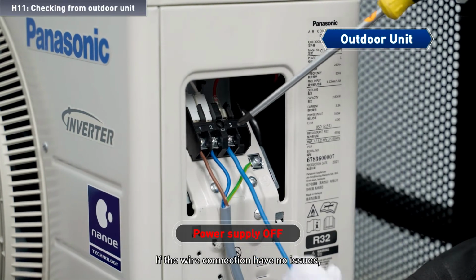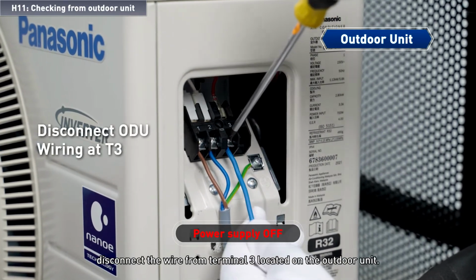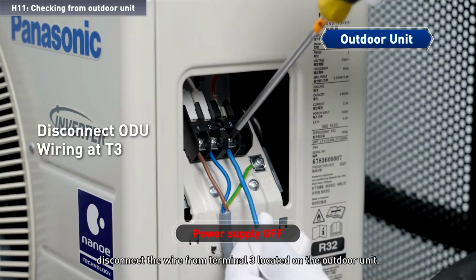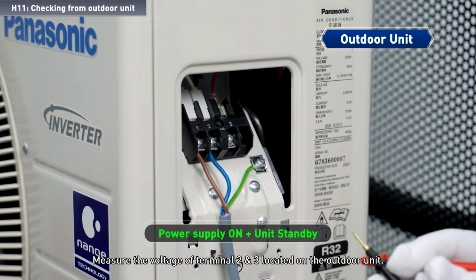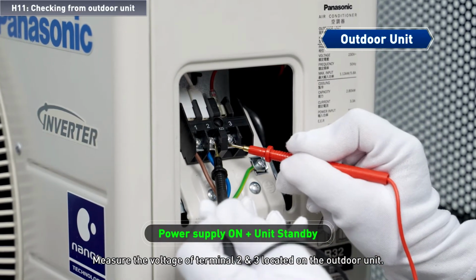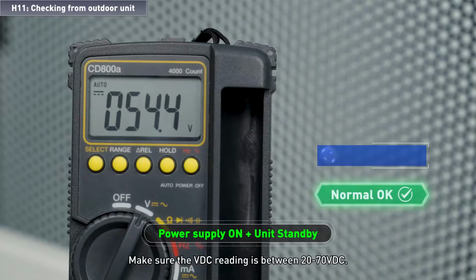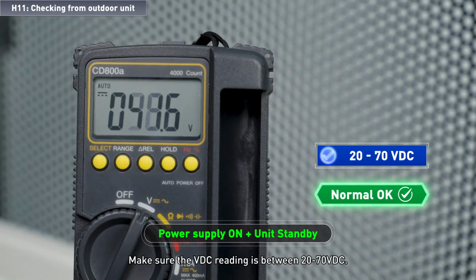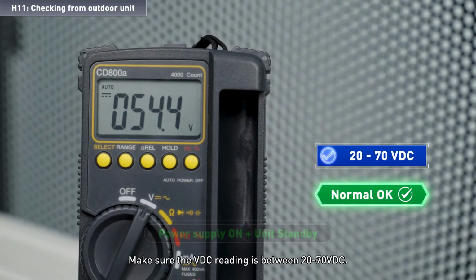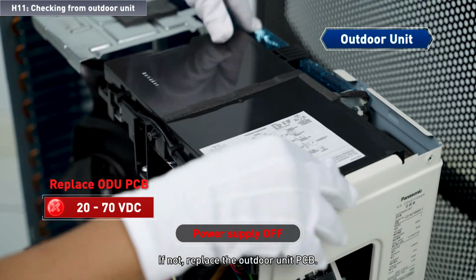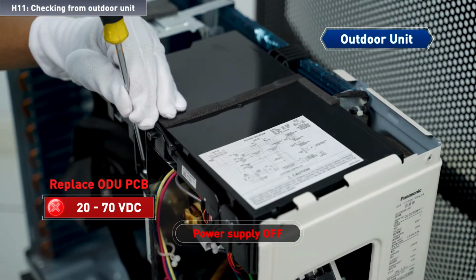If the wire connection have no issues, disconnect the wire from terminal 3 located on the outdoor unit. Measure the voltage of terminal 2 and 3 located on the outdoor unit. Make sure the VDC reading is between 20 to 70 VDC. If not, replace the outdoor unit PCB.